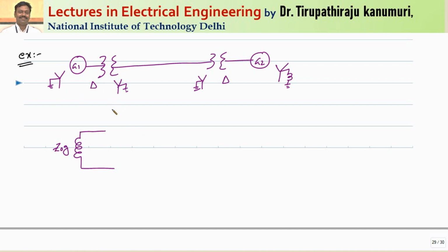So now coming to the transformer. For the transformer, the primary side is delta connected. As the primary side is delta connected, the series switch is open, but the shunt switch is closed. After this comes the zero sequence impedance of transformer T1, Z0T1, which I have represented. Now coming to the secondary side, it is star connected and solidly grounded, so it is short circuited like this. Now coming to your transmission line, this is the zero sequence impedance of your transmission line.